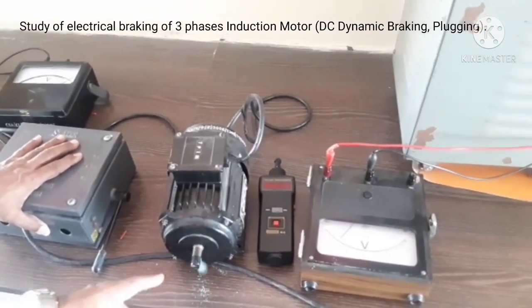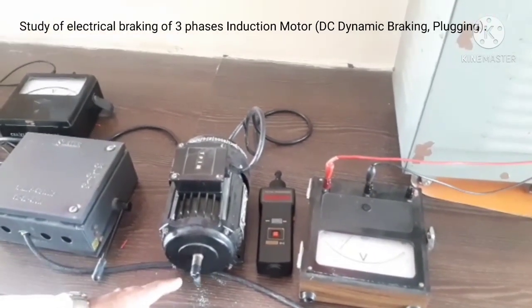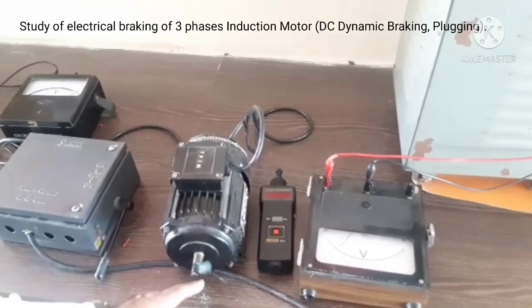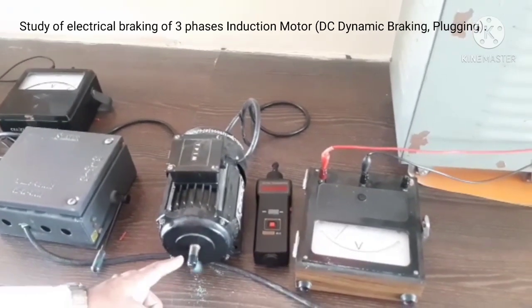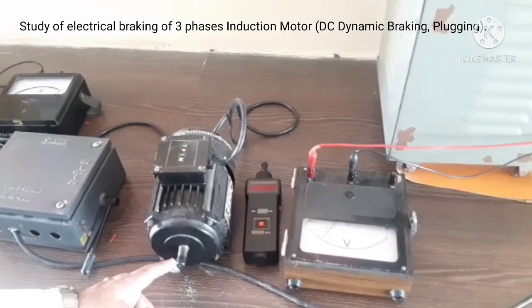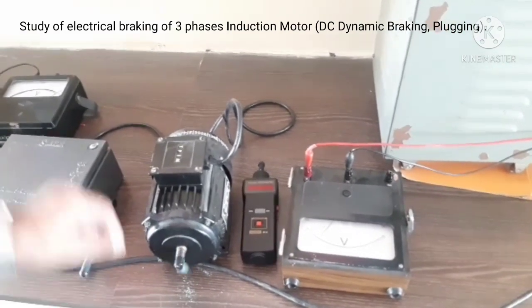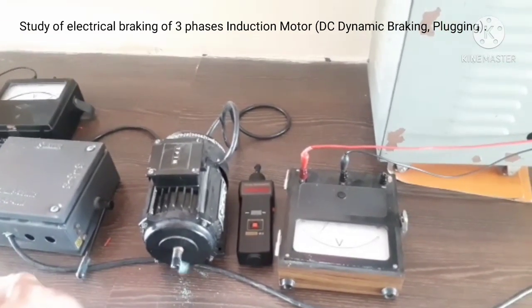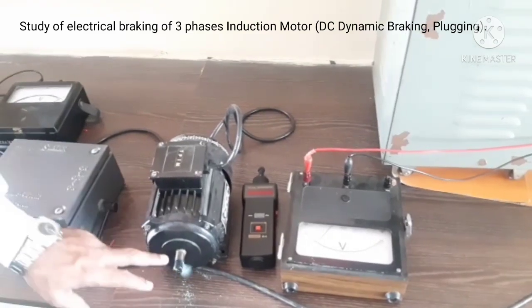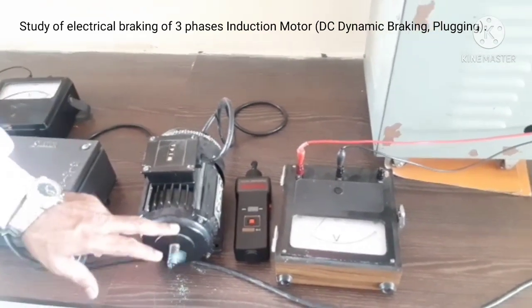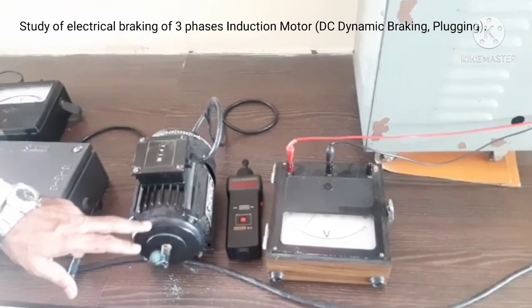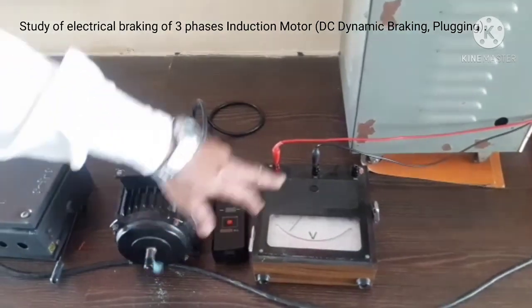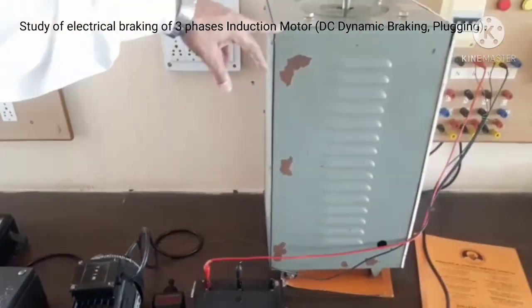Now see the time required—it is started rotating in the reverse direction. This means the characteristic has crossed the x-axis, and at that point you should stop the motor. The required time to stop this motor by applying 25 volts as reverse voltage is only 3 seconds.